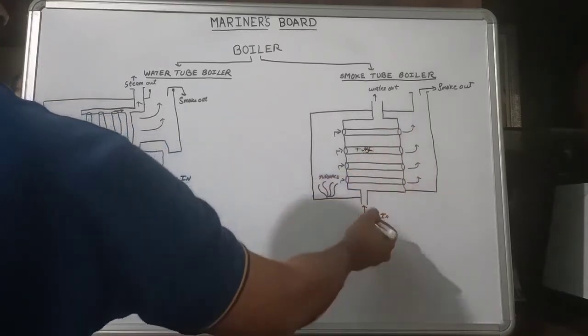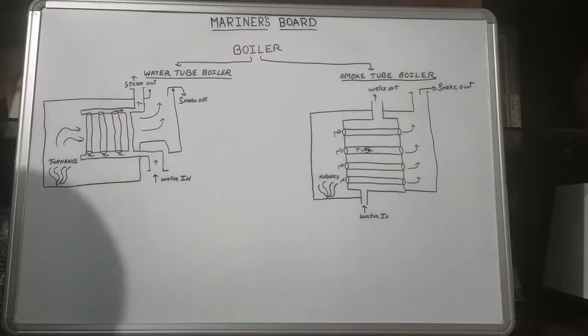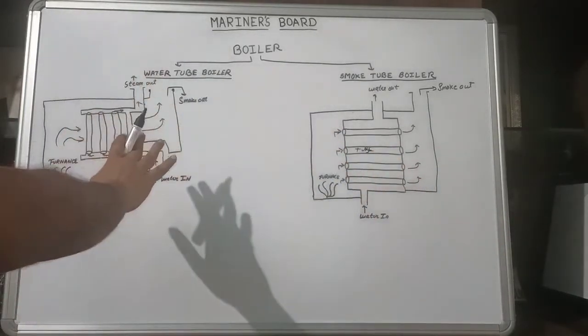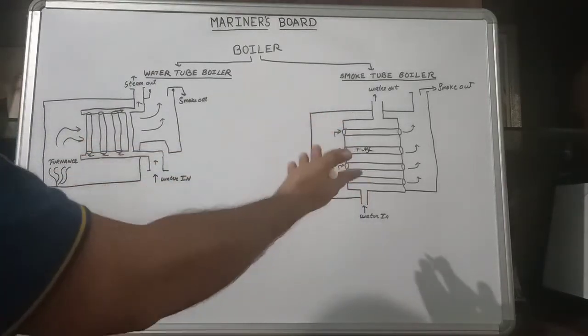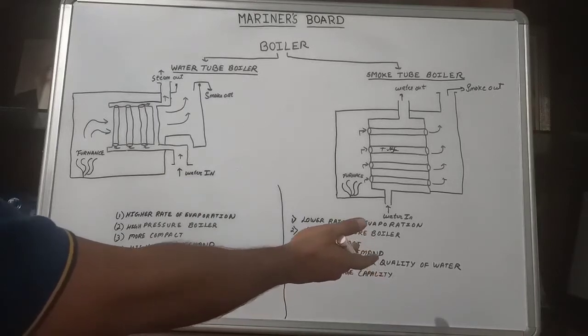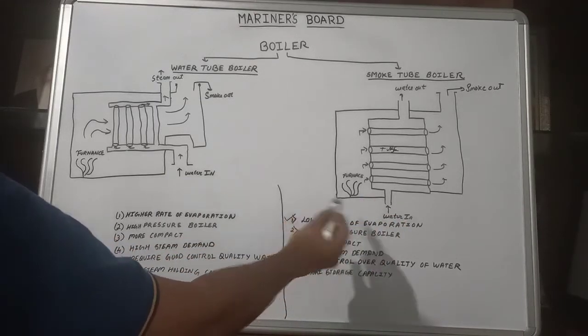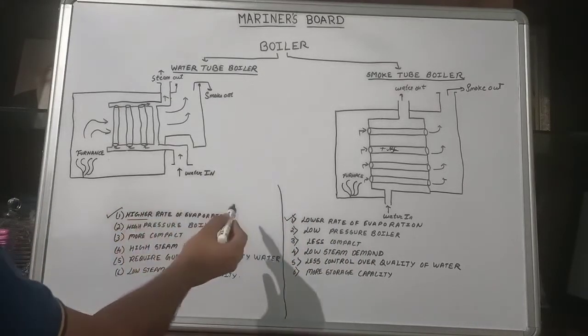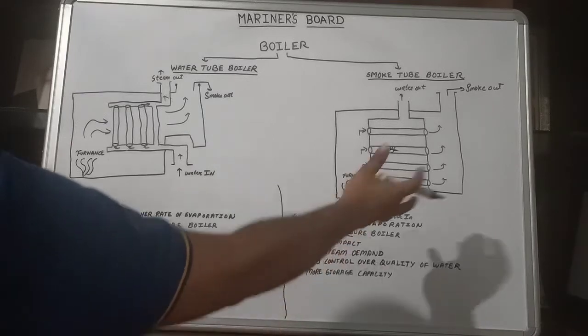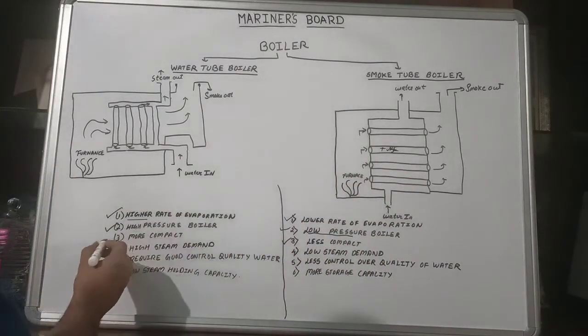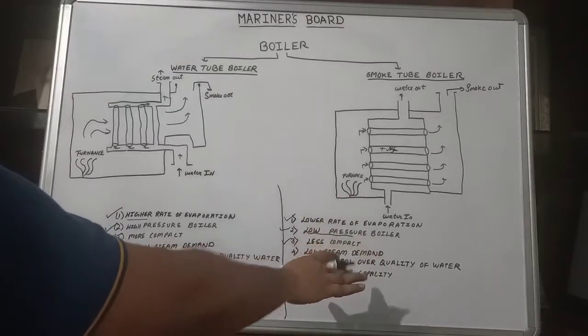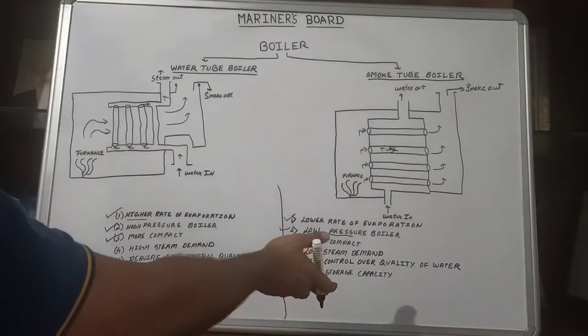A very important question a surveyor may ask is the basic difference between water tube and smoke tube boilers. Here are key differences: the smoke tube boiler has a lower rate of evaporation, whereas the water tube boiler has a higher rate of evaporation. The smoke tube boiler is a low pressure boiler, while the water tube boiler is a high pressure boiler. The smoke tube boiler is less compact in size, whereas the water tube boiler is very compact. The smoke tube boiler is mainly used where steam demand is low, and the water tube boiler is used where steam demand is high.